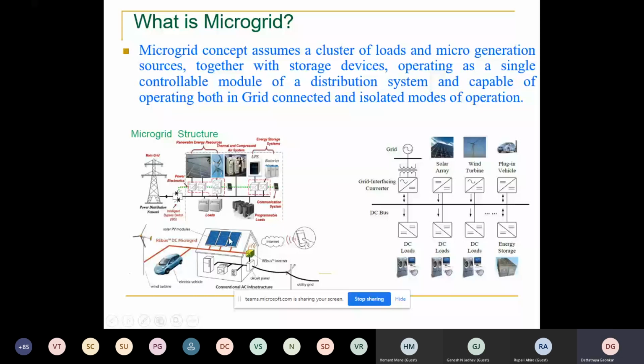The Bureau of Indian Standards is also coming up with DC grid standards, the voltage levels and everything. On a larger scale, you may have many generation and storage sources on a feeder or substation level, and that can become a grid. So the microgrid concept assumes a cluster of loads and micro generation sources together with storage devices operating as a single controllable module of the distributed system, capable of operating in both grid-connected and isolated modes.